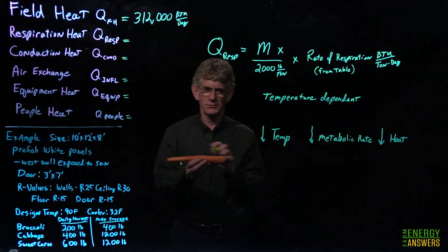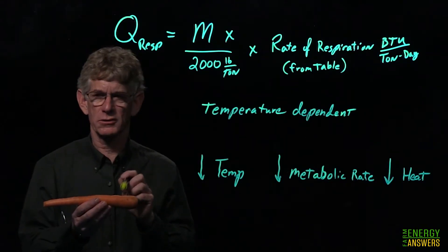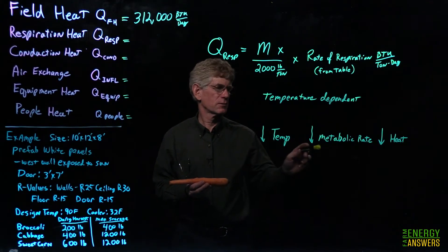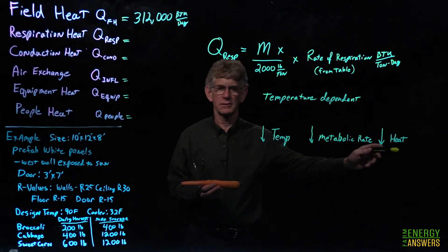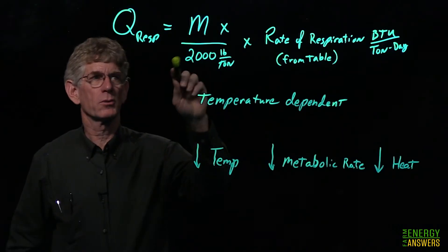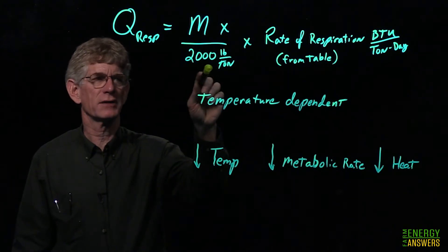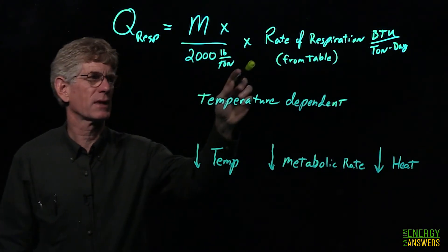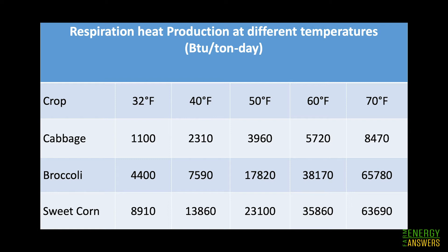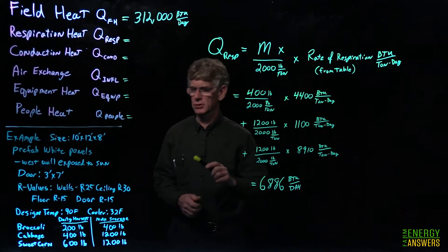Next we talk about respiration heat. Even though a carrot has been harvested, its cells are still active — they're converting stored sugars to heat. As temperature is reduced, the metabolic rate is reduced, heat generated is reduced, and the shelf life is extended. The formula is: (mass in pounds ÷ 2,000 lbs per ton) × the respiration rate, which you look up in a table after the product has been cooled and is being maintained in the cooler.